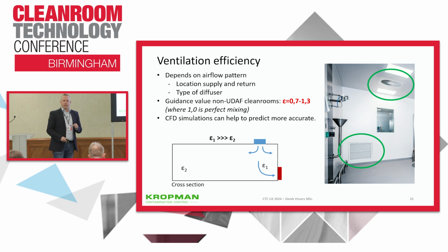And what about the second known unknown, the ventilation efficiency? It depends on the airflow pattern throughout your clean room. So it depends on the location of the supply and the return, but also on the type of diffuser. I think you can all imagine in this situation, if this is a cross-section of your clean room, that the ventilation efficiency in location 1 is much higher than in location 2.